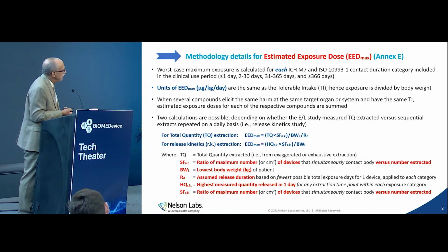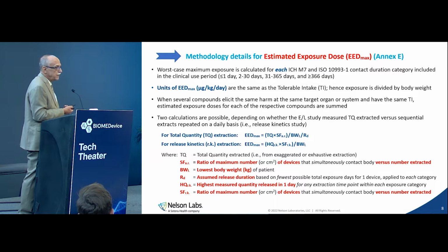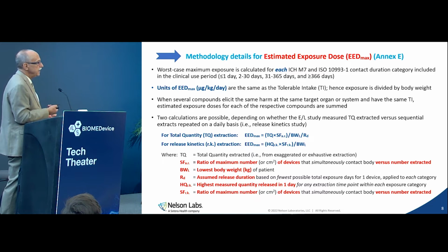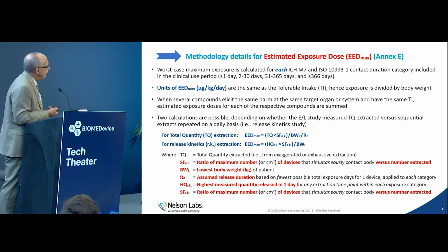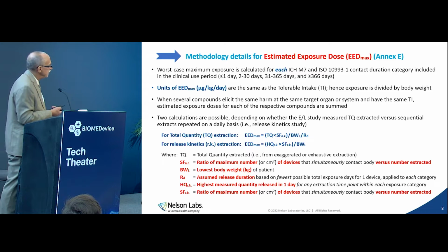There's also a possibility that you had a more sophisticated chemistry test where you extracted in 24-hour increments representing 1 day increments of patient exposure. And in that case, the second equation, you take the highest quantity detected from any 24-hour time point from your chemistry results.